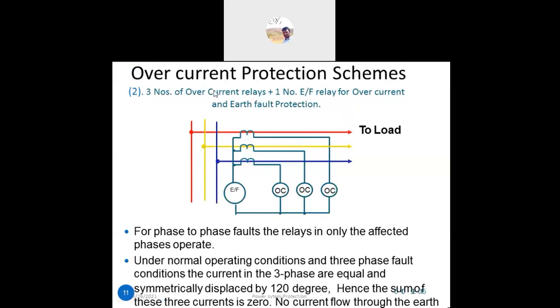Another protection scheme uses three overcurrent relays plus one earth fault relay. For phase-to-phase faults, only the affected phase relay operates. Under normal operating conditions, the three-phase currents are equal and symmetrically displaced by 120 degrees. The sum of the three-phase currents is zero, so no current flows in the earth fault relay under normal conditions.